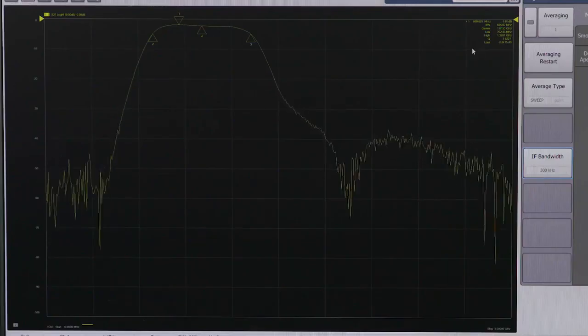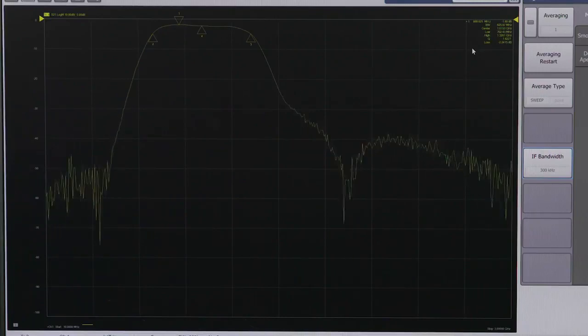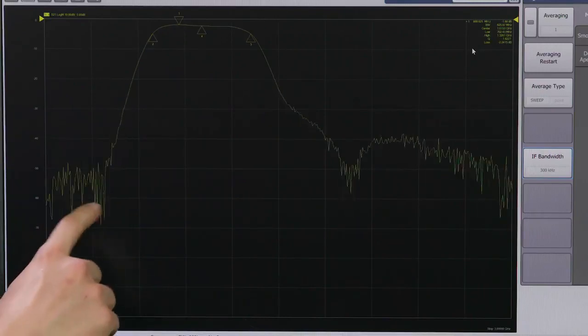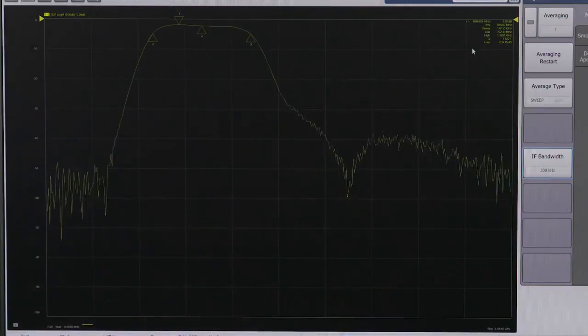However, the tradeoff is the higher the IF bandwidth is set, the more random noise will be introduced to the measurement. You can see that increased noise here in the rejection bands below 350 MHz or above 2 GHz.